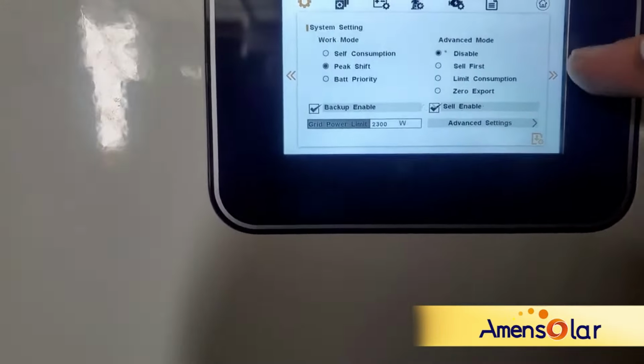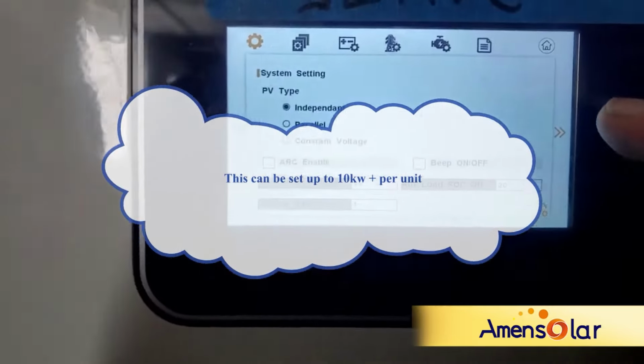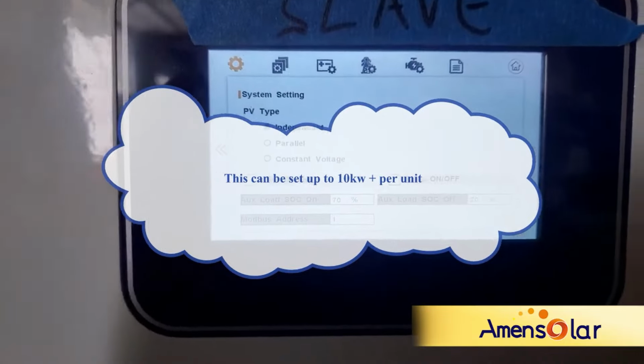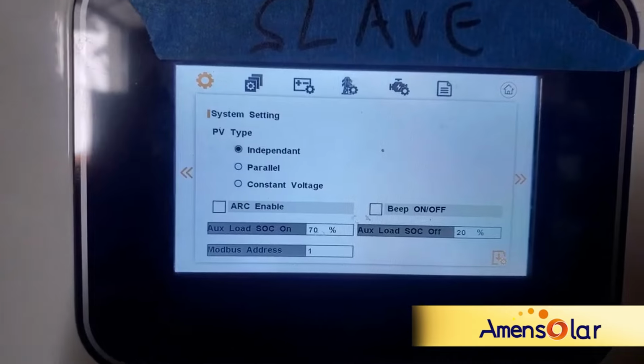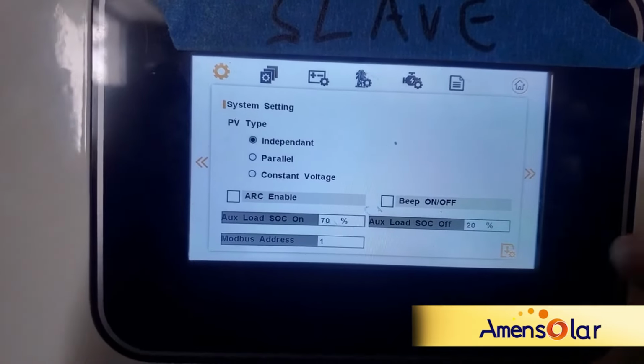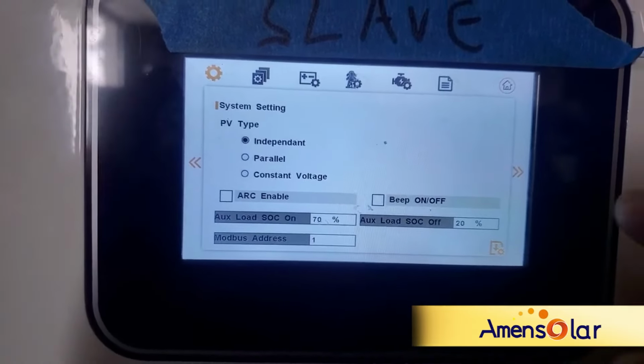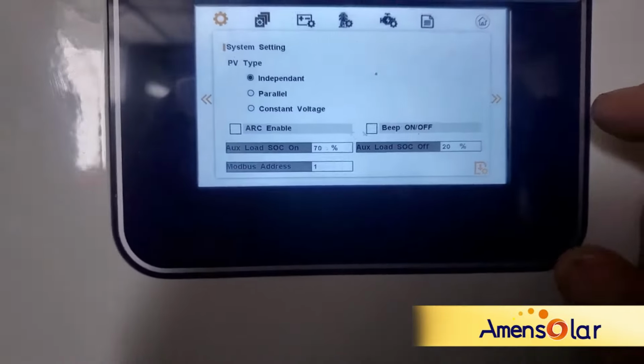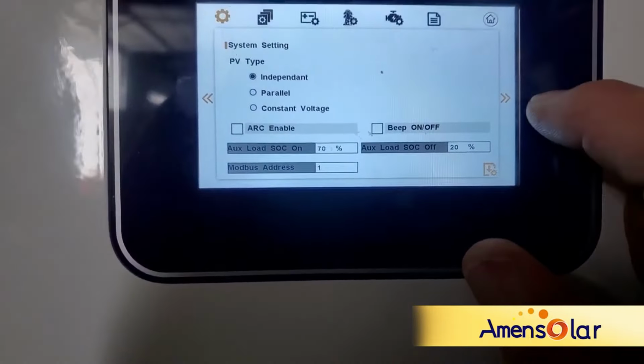And I've got my export set and my PV type. You can set it to independent, parallel, or constant voltage, depending on if you're using optimizers. Some of them want to run at constant voltage, otherwise I run them independently or parallel. If you've got a whole lot of strings together, you want to run it parallel. You can just see which one's going to give you the best output.